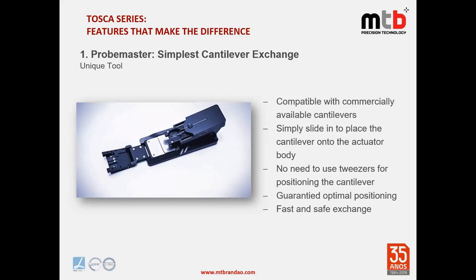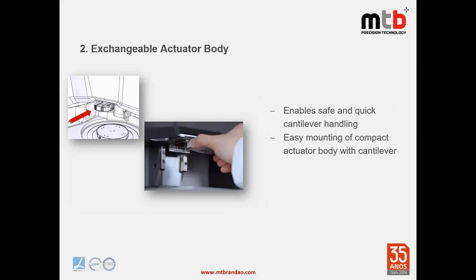For some instruments on the market, the user needs to handle the entire instrument head, but with TOSCA this is not necessary — only the actuator body needs to be removed. A very important but complex step when performing AFM measurements is laser alignment, which can be time-consuming especially for inexperienced users. Therefore, TOSCA provides a fully automatic laser alignment function. After loading the cantilever onto the actuator body and placing it on the AFM head, the instrument carries out laser alignment automatically after just two clicks in the software.